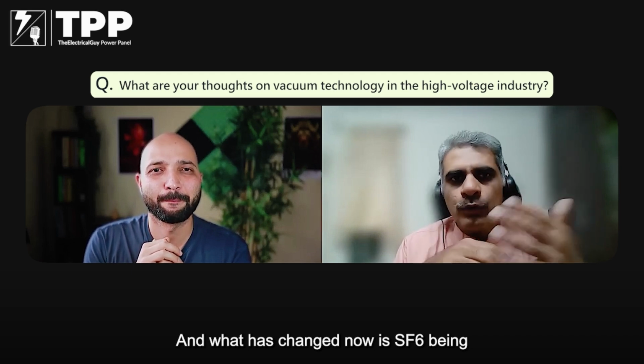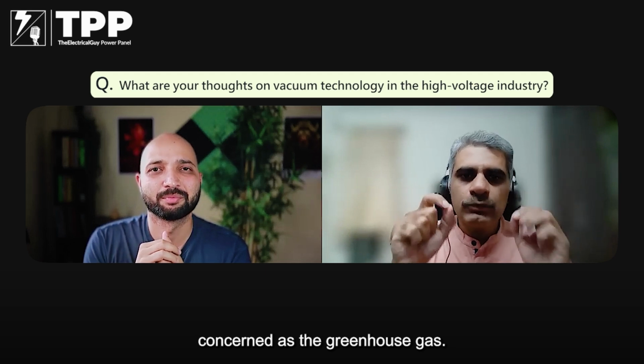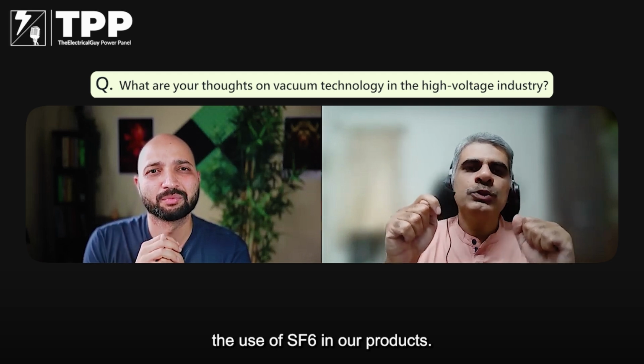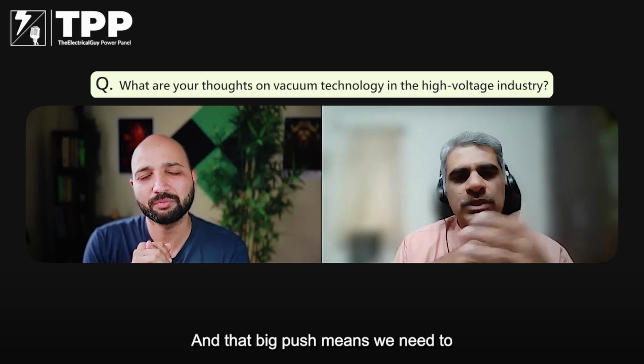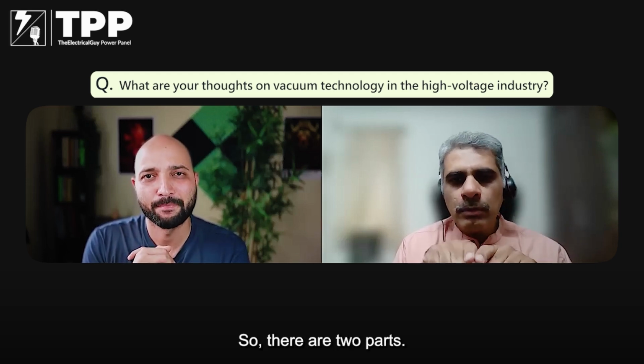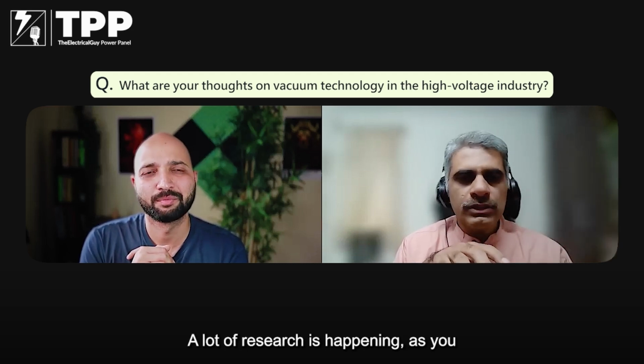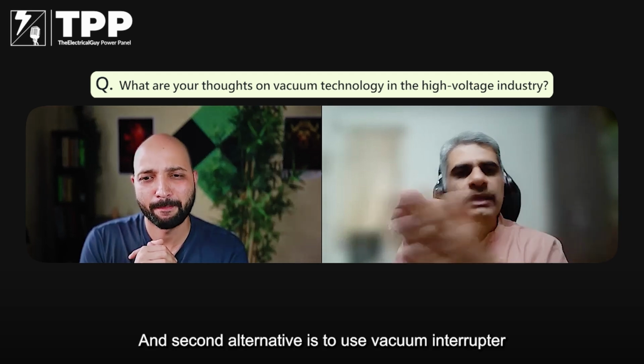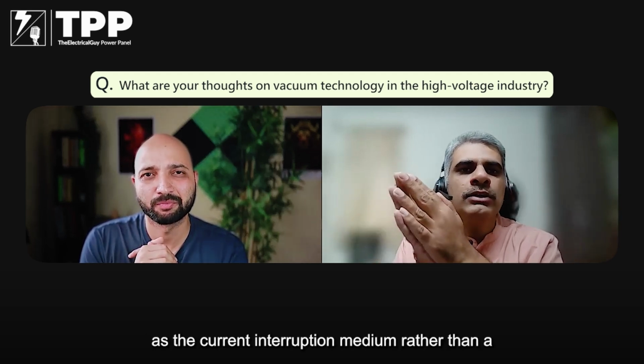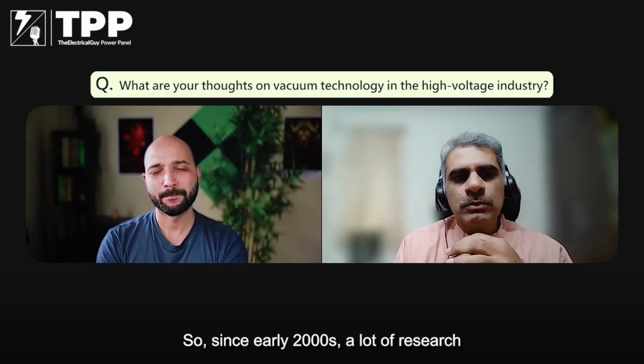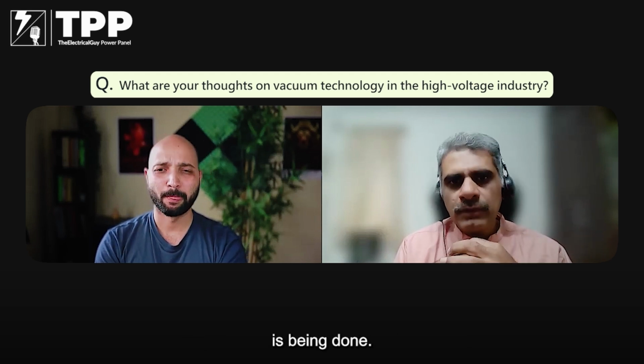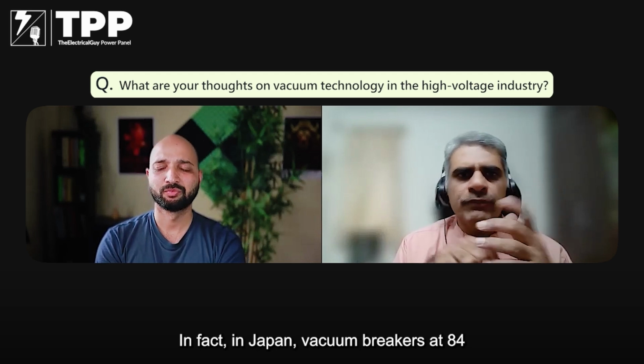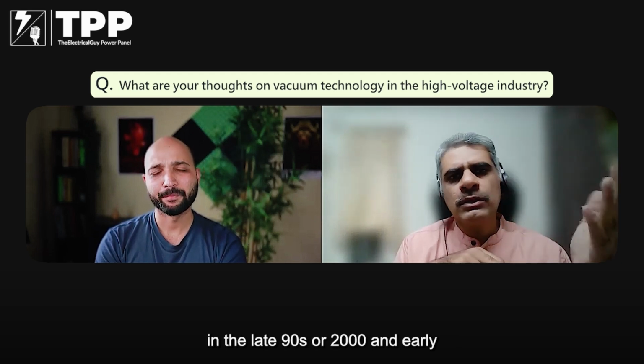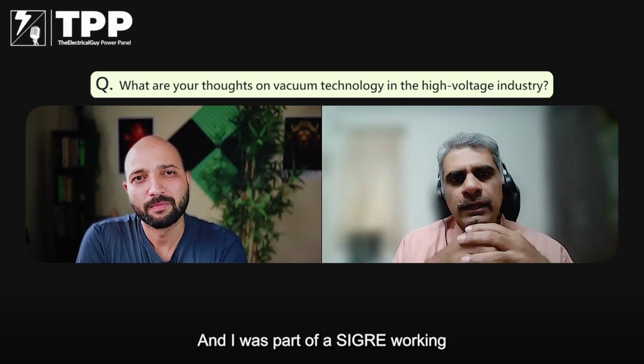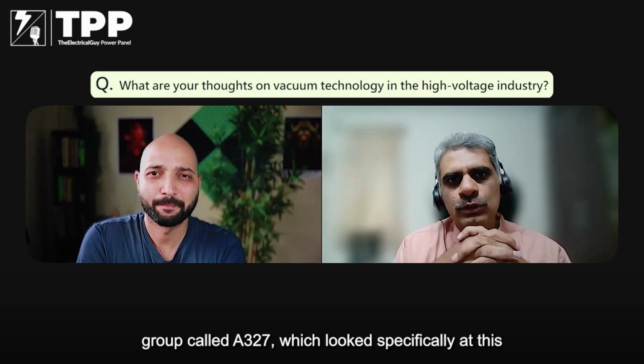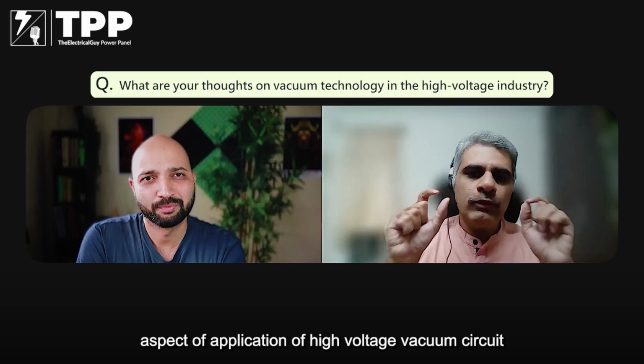And what has changed now is SF6 being considered a greenhouse gas. So there's a big push to reduce the use of SF6 in our products. And that big push means we need to find alternatives to SF6. So there are two paths. One, we find an alternate gas. A lot of research is happening, as you know, on that front also. And the second alternative is to use the vacuum interrupter as the current interruption medium rather than a gas. So since the early 2000s, a lot of research is being done. In fact, in Japan, vacuum breakers at 84 kV or maybe even 145 kV were used in the late 90s or 2000 and early 2000s also. And I was part of a CIGRE working group called A3.27, which looked specifically at this aspect of application of high voltage vacuum circuit breakers.